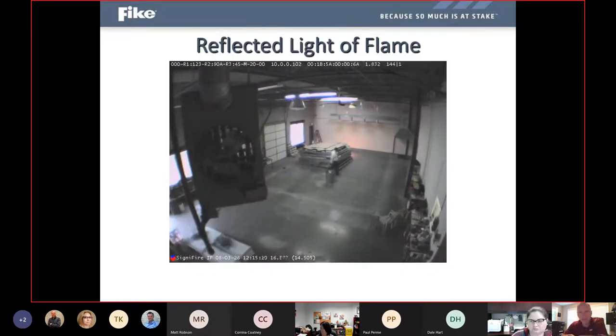And then with the reflected firelight algorithm, here you can see a fire has been lit behind that stack of boards. Even though we cannot see the flame directly, the software is looking for that random flicker and reflective patterns on surrounding surfaces and is outlining it with those purple hash marks. It would now be triggering folks to realize, hey, I don't see smoke, I don't see a visible flame, but this has all the lookings of a fire occurring behind an obstruction or a piece of machinery that's worth someone going to check out and take a look at.